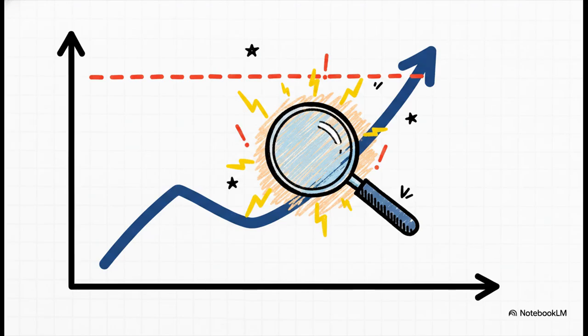And this brings us to the single most vital compliance takeaway across every single utility we have discussed today. Individual passing results are simply not enough. A single test only tells you the state of the system at that exact millisecond in time. You must trend your data relentlessly. Trending is what reveals the invisible story. It's what allows you to catch systems that are slowly drifting out of specification long before they actually fail and compromise your product.